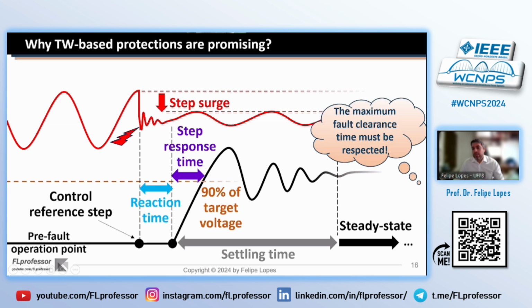So the second option would be only to accelerate the protection. And in this case, using these fault-induced transients, which usually show up during the reaction time of the IBRs, comes to be very promising, especially because these transients are not affected by the source characteristics, and so the protection decisions could be made before the controllers start their actions.